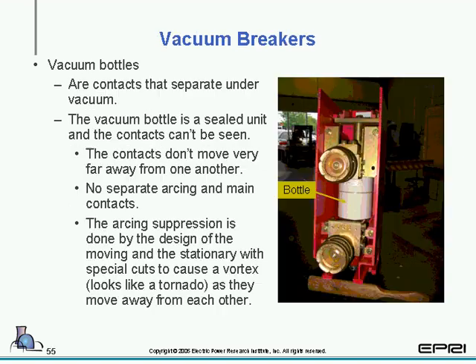When you open a circuit breaker under load, you're trying to break the arc, and you can either use an air magnetic breaker or you can use SF6, sulfur hexafluoride gas, or vacuum, or oil. So that's the key thing to remember here. Sorry, Gene. All right, and then the last one we're going to take a look at, the second to last, is the vacuum breaker.